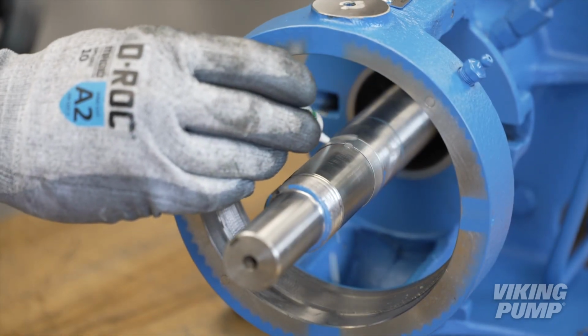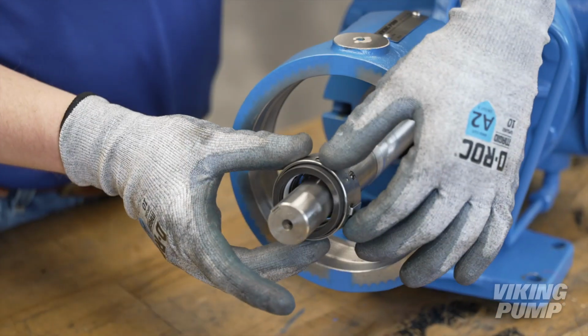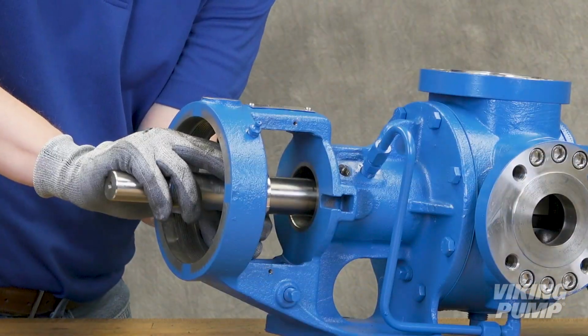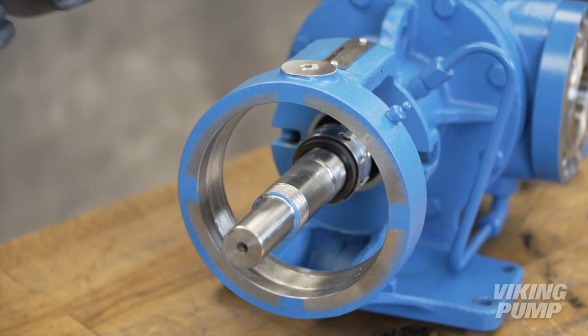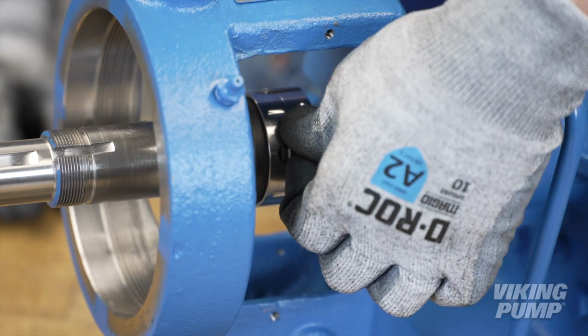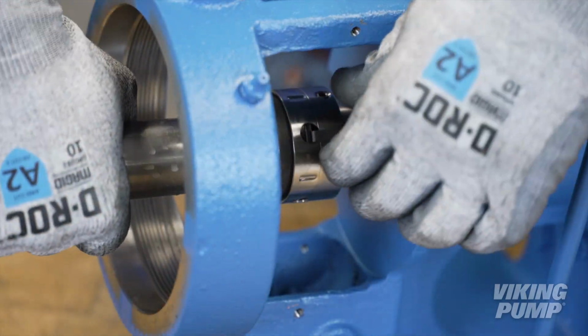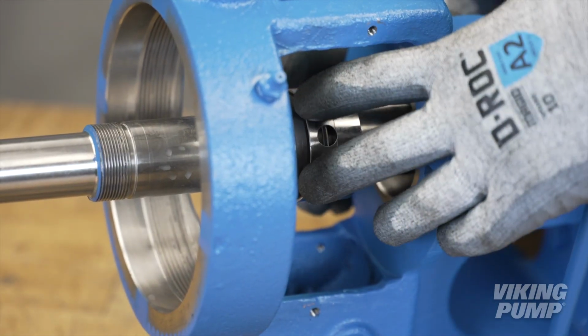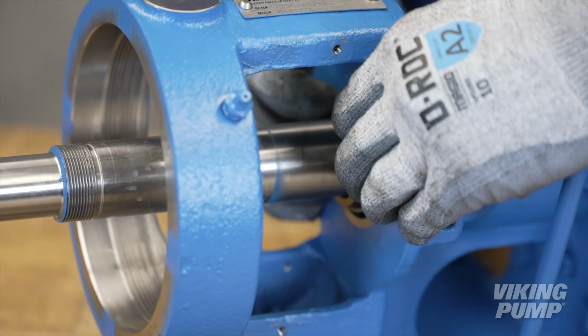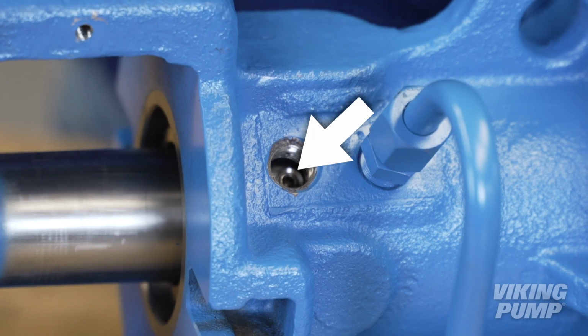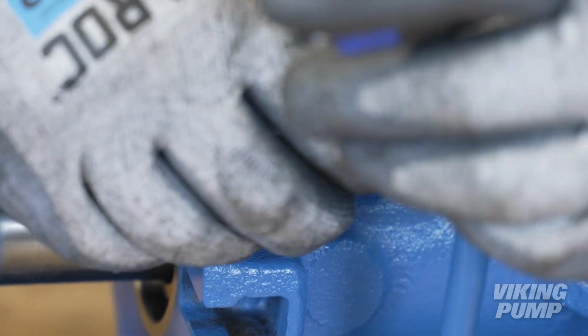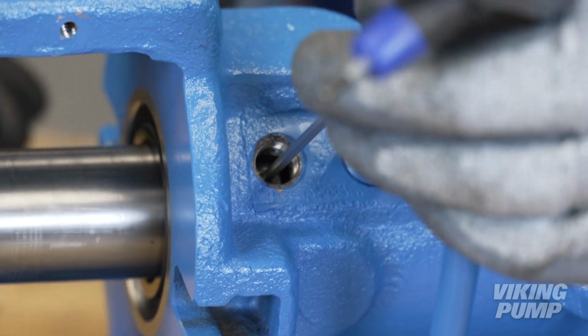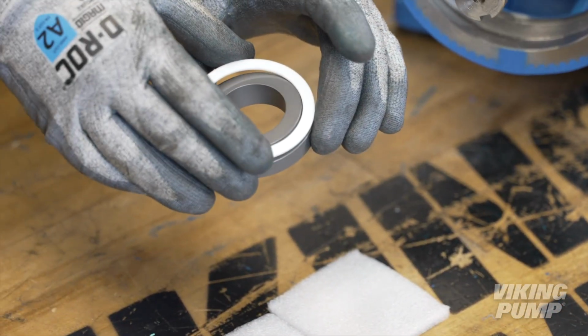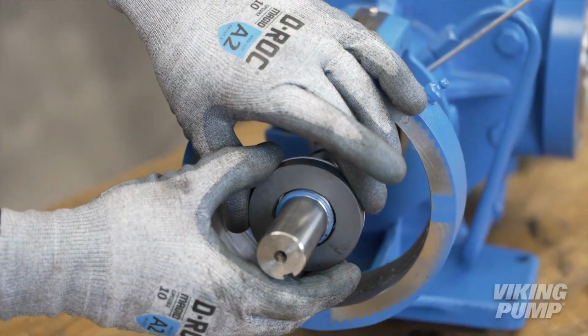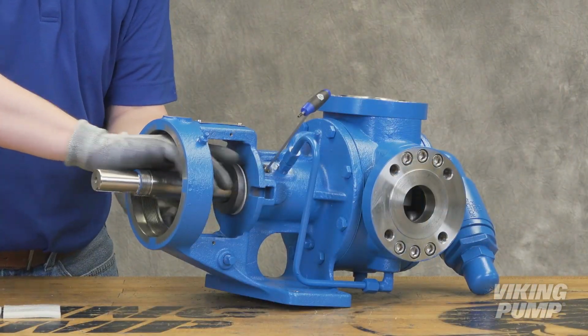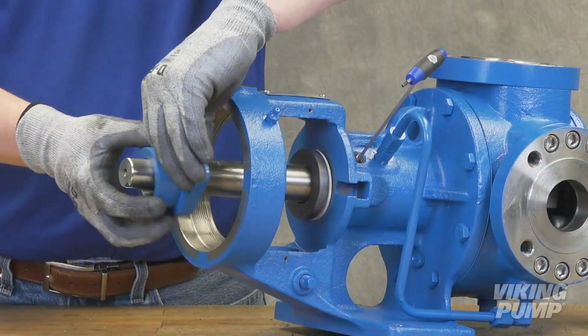Lubricate the shaft and install the rotary member of the mechanical seal. Remember to remove the seal installation sleeve. Before reaching the bracket bore, remove the 4 seal clips to engage the seal. Finish installing the seal until the set screws line up with the seal access hole in the bracket. Insert a hex head wrench into a set screw to keep the seal from sliding as you complete the rest of the installation. Next, place the PTFE gasket around the stationary seal seat and slide onto the shaft. Install the gasket into the seal holder and slide onto the shaft.